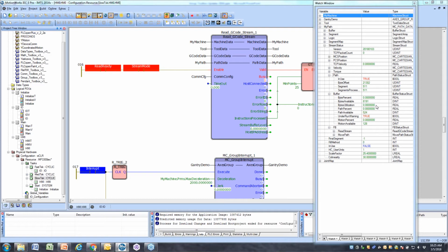It indicates that it's more stable in terms of surges in data being processed. If the number was high, that would mean it's quite busy and trying to process every scan. And if it's quite low, that means that the data is kind of coming in these spurts that make the block run harder on infrequent scans. So byte utilization somewhere in the middle percentage is ideal.